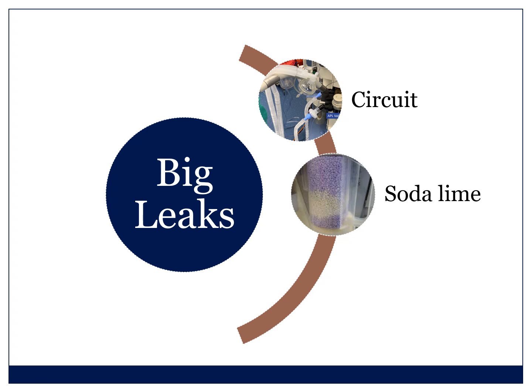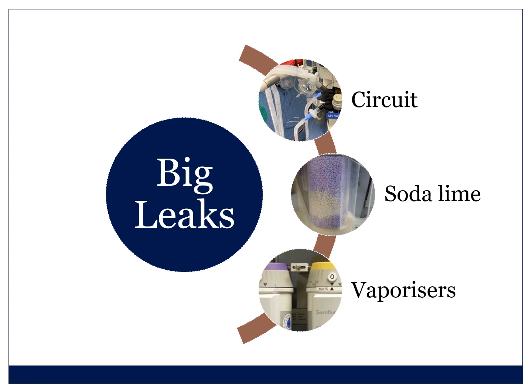And you can get a leak so big you don't even hear the leak there. And then thirdly, the vaporizers. If a vaporizer is not seated properly, you can have a massive leak at that place where it's seated, and you won't realize it. So those are the 3 big causes of leaks.